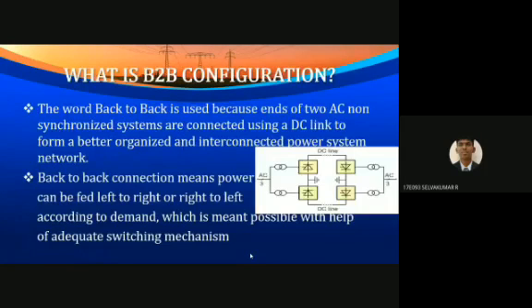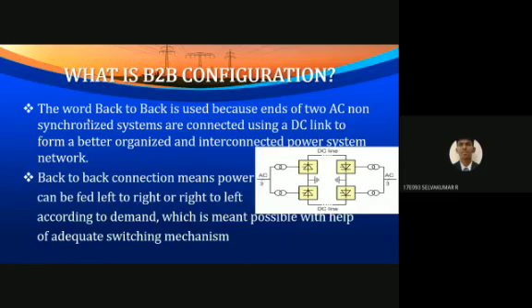First, what is back-to-back configuration? As you can see in this image, AC supply is given as input and AC supply is given as output. These both input and outputs are interconnected using a DC line. The word back-to-back is used because ends of two AC non-synchronized systems are connected using a DC link to form a better organized and interconnected power system network. Back-to-back connection means power can be fed left to right or right to left according to demand, which is made possible with the help of an adequate switching mechanism.